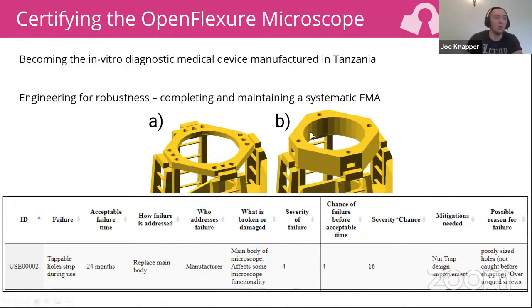Here you can see one example of this, where before we would screw sample holders directly into the stage, but we found that this can strip the threads inside, which prevents the sample from being held properly. So instead we updated to this design, where you can use nuts to screw into, holding the sample in place more reliably.